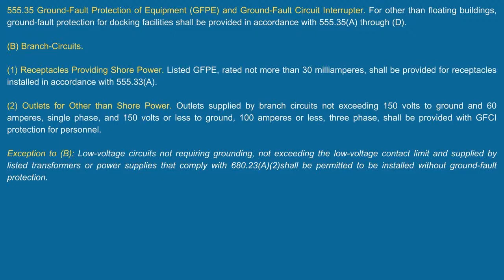That means I'm going to be cord and plug connecting something. Is that correct? Yes, sir. Okay. And it says, if I'm going to shore power, listed ground fault protection of equipment not rated more than 30 milliamperes shall be provided for receptacles and installed in accordance with 555.33(A). And that's where, if you already provided upstream with a feeder, you're okay, right? And then you can dial it down to whatever you need to match it.